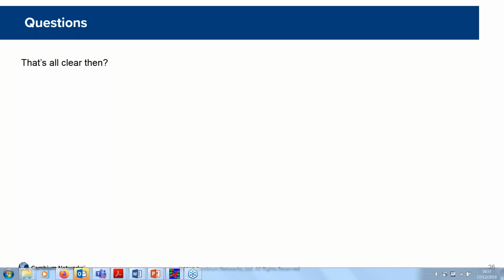There was another comment asking if they can use the same cable from the top of the tower to connect the ground for LPU and ODU. So we have a drop cable from the LPU down the tower, which would have a shield on it, and we have a cable then which is going from the LPU to the radio, to the ODU, which shouldn't be longer than about 2 feet. I would have thought that that would be best made from the same type of cable. I can't think why one would want to use a different cable to connect from the LPU to the radio. So I think the answer is yes, it should be the same cable type.